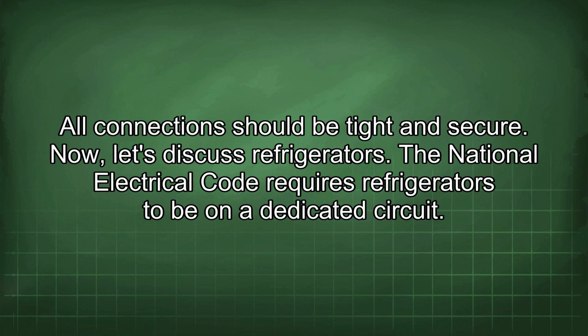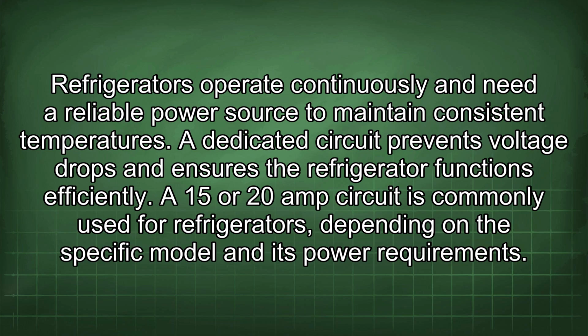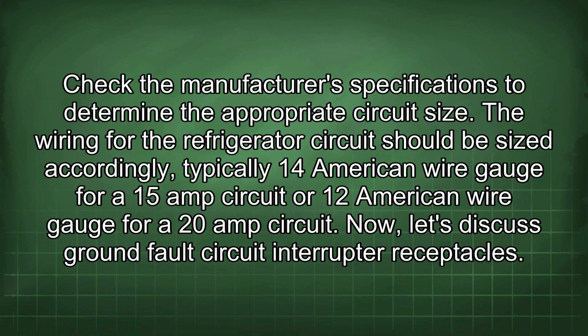Now, let's discuss refrigerators. The National Electrical Code requires refrigerators to be on a dedicated circuit. Refrigerators operate continuously and need a reliable power source to maintain consistent temperatures. A dedicated circuit prevents voltage drops and ensures the refrigerator functions efficiently. A 15 or 20 amp circuit is commonly used for refrigerators, depending on the specific model and its power requirements. Check the manufacturer's specifications to determine the appropriate circuit size.